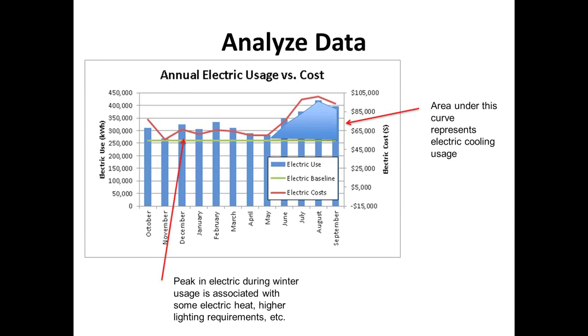Looking at the shoulder season, knowing that this is in a northeastern climate, where the predominant energy use is going to be heating based on outside temperature, but there is also going to be a cooling load associated with internal heat gains. We can determine a base load by looking at the shoulder seasons, November, April to May, the periods where electricity usage was the lowest. We know that these are going to be the months where the building did not respond to outside temperatures, because temperatures were right around that 65-degree mark.